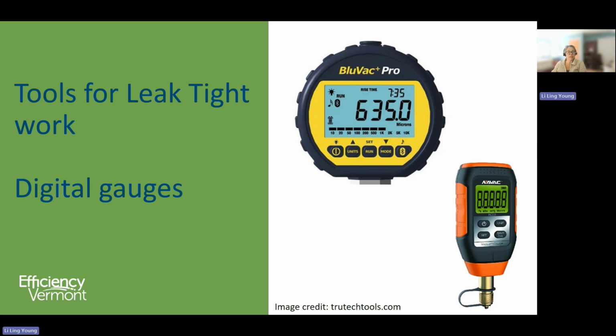And the pressure gauge releases much less refrigerant from the system than a manifold gauge set, if you have to measure pressure at all. Don't use a manifold gauge set for measuring system pressure. There are just too many places in a gauge set that could leak, and the length of hose bleeds refrigerant out of the system.